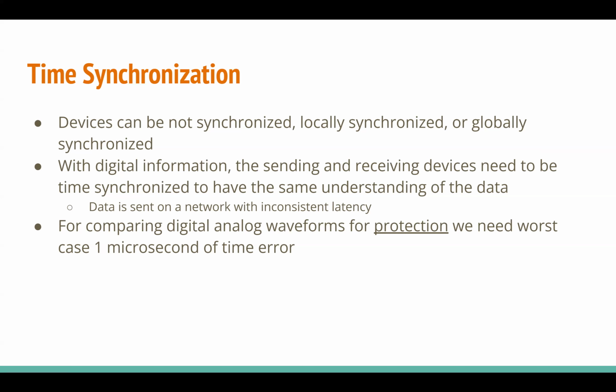The problem is that if we want to compare data between relay A and relay B, and they think it's different times, then for continuous data, like a voltage or a current, you would end up having an offset. I'll show you that on the next slide. That would be an issue if they were not synchronized. Then there's the term locally synchronized. That means relay A and B in the same location can talk to each other and agree that it's 12:01, but that doesn't necessarily mean it's actually 12:01. They could both agree it's 12:01 even though it's 12:05. That means they can compare data against each other, but they can't compare data against things outside in the world.